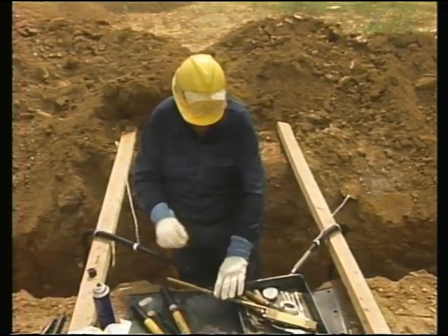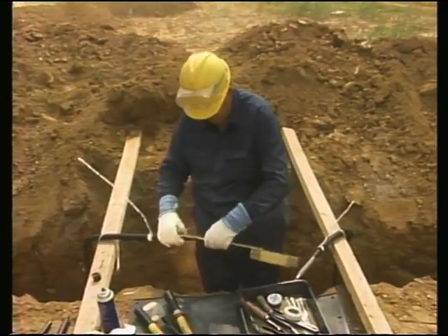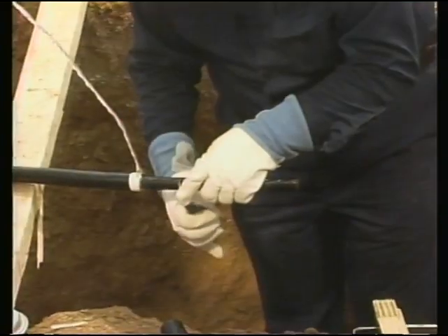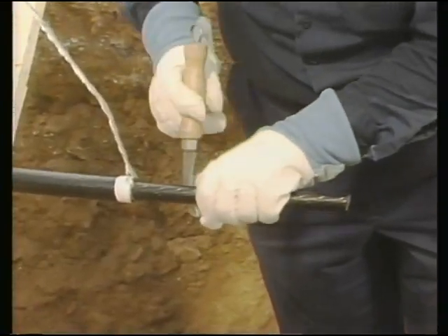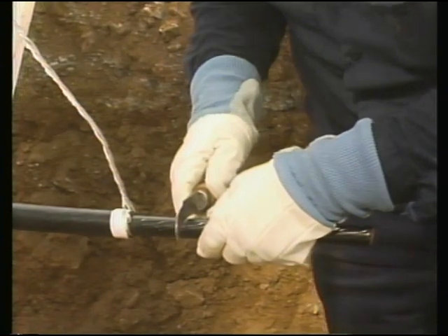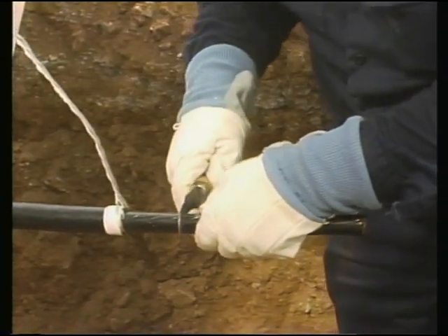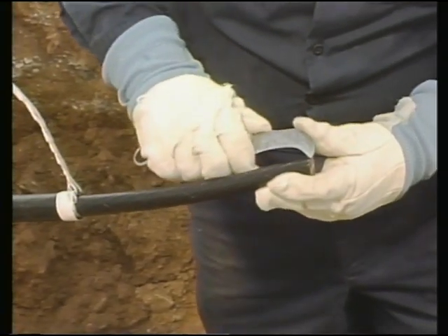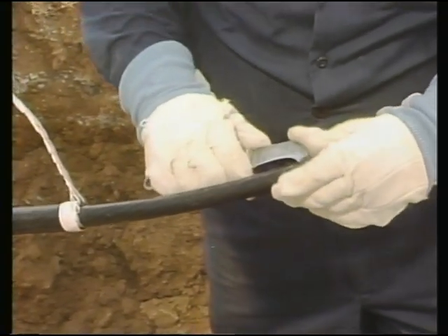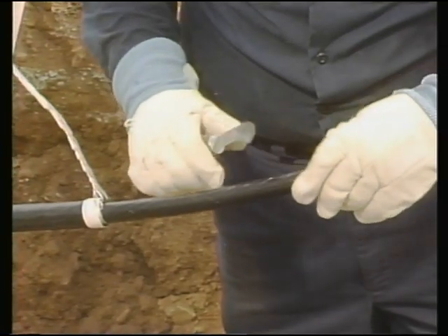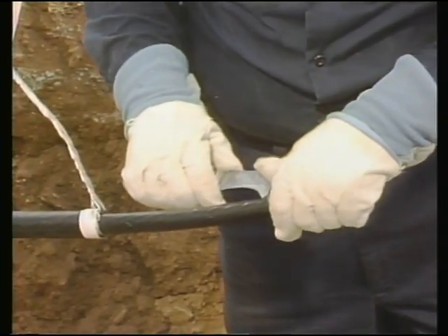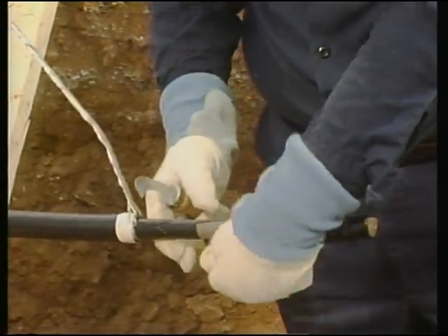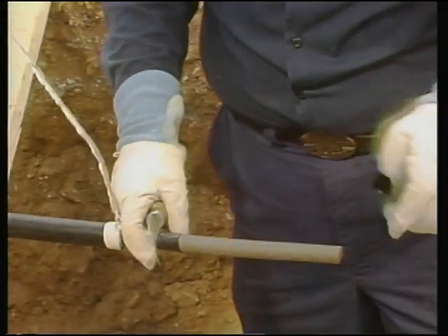The directions say that the workman is then to take another measurement and place his next mark on the semiconductive shield layer. The semiconductive shield is then removed at the mark. If a knife is used, the semicon layer is scored lightly at the mark and down through about half the semiconductor layer's thickness. Then over to the end of the cable, making a weak point in the layer. Extreme care must be taken not to score or nick the cable insulation below. It can then be removed by pulling and breaking at the weak point.